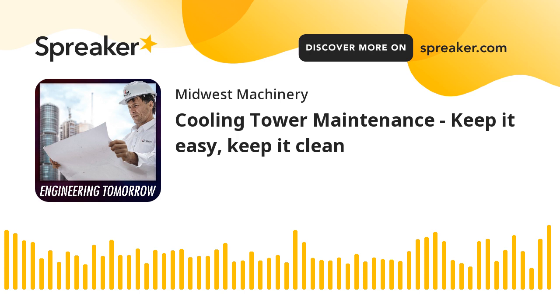It's going to be an open spot for things to enter, and it's obviously hard to keep a cooling tower clean year-round. So this is going to be getting in there and actually cleaning it or looking at it. Or, for instance, you're going to need to do blowdown. So blowdown is to get rid of that built-up concentration of dissolved solids in your cooling tower water.